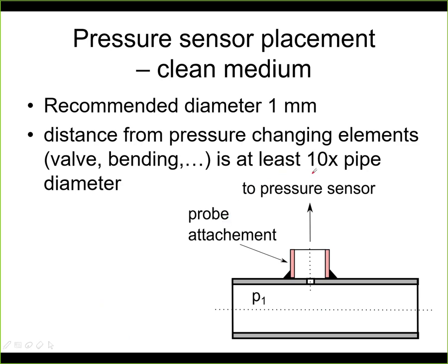We need to keep this distance to be at least 10 times the pipe diameter, and this applies for clean liquids. So if we want to measure the pressure, let's say here we have a pipe and I want to measure the pressure of some fluid in this pipe, I will attach the probe in this place. So anything before and after the flow, such as a valve or bending, could have an effect on the pressure that I measure. So the recommended distance is at least 10 times pipe diameter. Then the recommended diameter for this pressure tap is about 1 millimeter. And again, this applies only for clean liquids, for clean mediums. Of course, if you have some particles in there, now this might be too small, and you may block this opening with some dirt, for example.